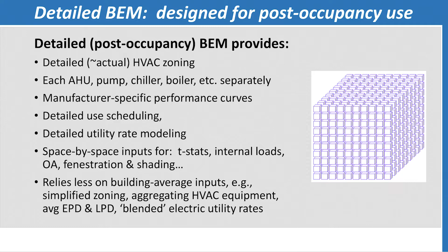Detailed scheduling, manufacturer equipment-specific performance curves for that model of chiller, that model of boiler, and so on—not just under standard conditions, but under the conditions you're actually operating it for. So you normally have to go back to the manufacturer for that kind of information. Detailed use schedules, detailed utility schedules as well.